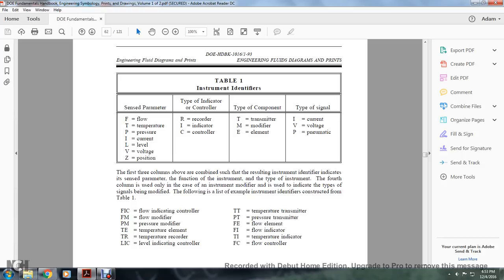Examples of identifiers constructed from Table 1: FIC is flow indication controller; FM is flow modifier; PM is pressure modifier; TE is temperature element; TR is temperature recorder; LIC is level indicating controller; TT is temperature transmitter; PT is pressure transmitter; FE is flow element; FI is flow indicator; TI is temperature indicator; FC is flow controller.